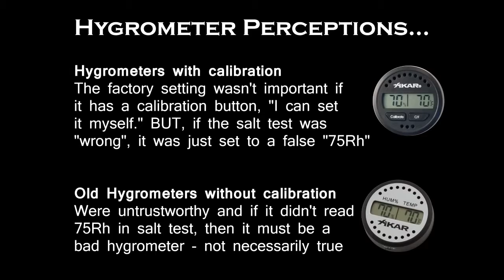Yeah. And what we found was sometimes that calibration process was a little confusing. Sometimes there were little things that could go wrong and you'd have really big errors. So you get kind of a false reading or a false positive on what you were getting. Right. So every time you would calibrate the thing, you would push a button and it would tell you 75%. Congratulations, you're calibrated, whether it was really 75% or not.